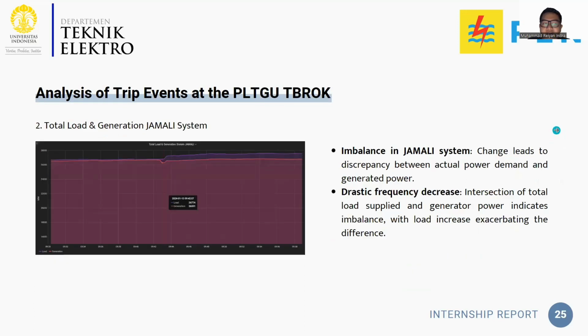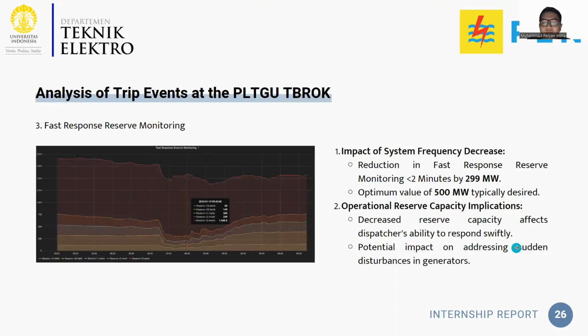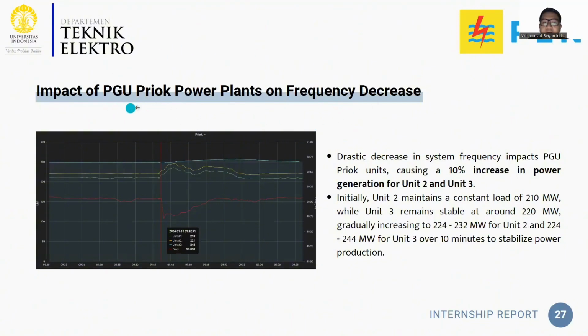And this will also affect the total load and generation of the Jamali system, as well as the overall system of the Jamali. And it shows the imbalance of the Jamali system, as well as the intersection of total load supplied and generation power, which indicates imbalance with load increase. And that also affects the fast response reserve monitoring, the reserve power for the generation, which has an optimum value of 500 megawatts, but it dramatically drops to 299 megawatts. And also, it has several impacts on the other power plants, such as the PGU Priok. And we can see that these generation units tend to increase, as well as the reductions in the frequency system, in order to make a balance between the load and generation demands.